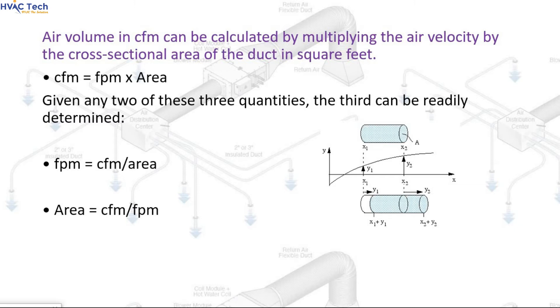CFM equals FPM × Area. Given any two of these three quantities, the third can be readily determined: FPM equals CFM divided by Area; Area equals CFM divided by FPM.